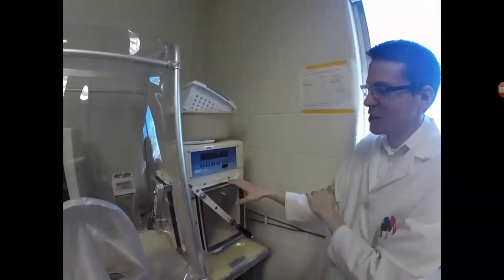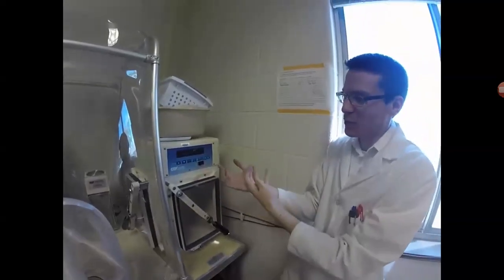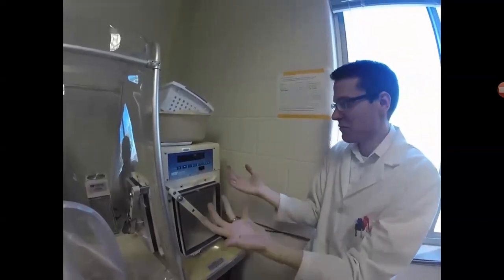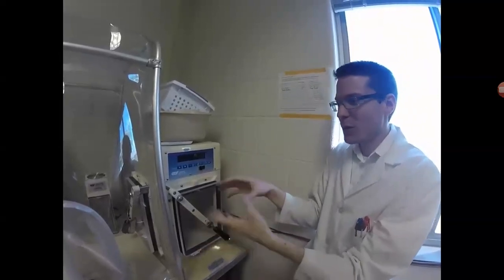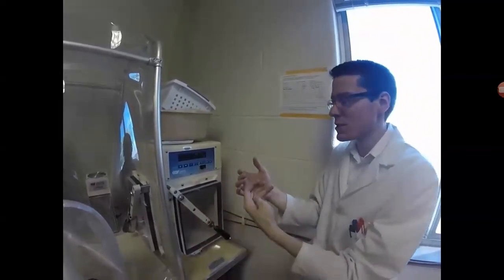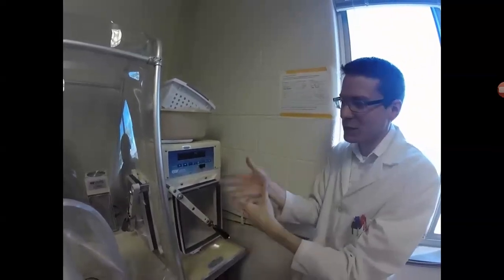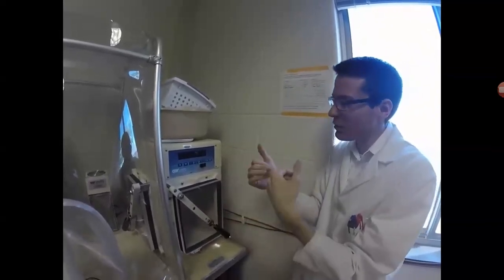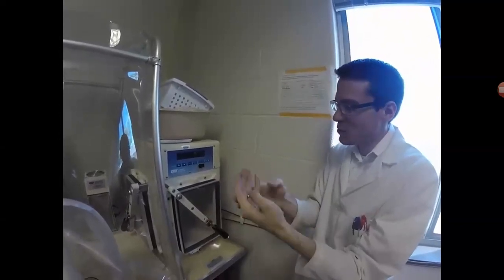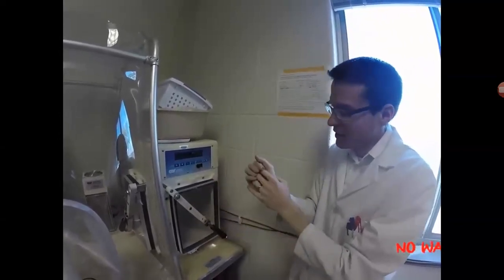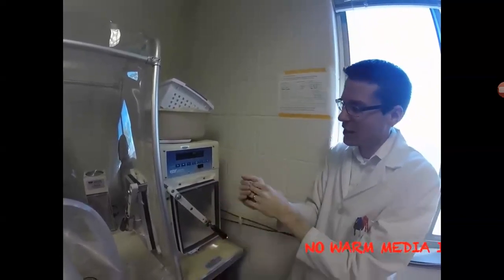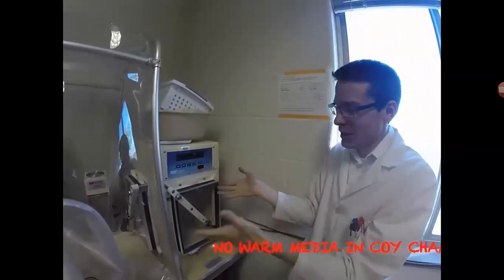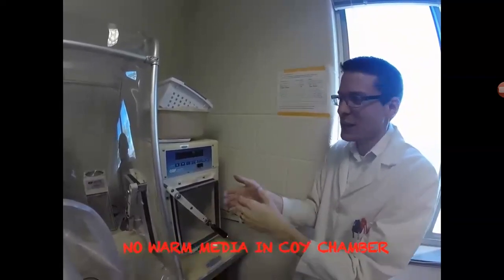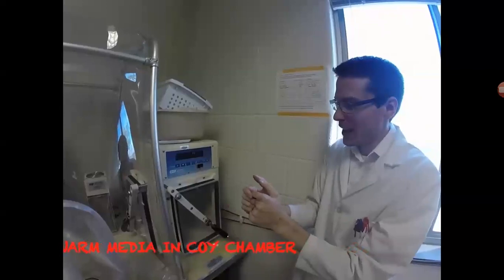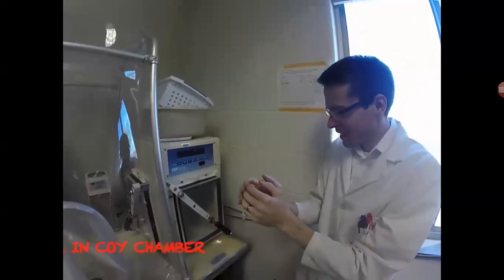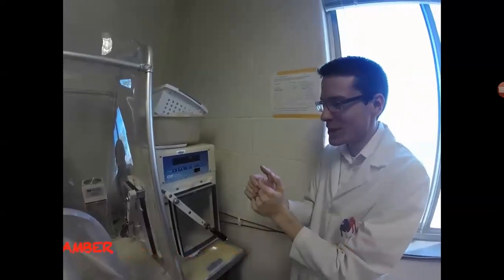A few things to mention are that it does pull a vacuum of 20 inches of mercury, which is fairly significant. So for typical things that are sealed, like media bottles and stuff like that, I will loosen the cap just to allow gas to exchange. It probably helps to remove oxygen as well. If you were to ever bring warm media in here, so let's say you took something out of the autoclave and it was still decently warm, you need to remember that under low pressure inside of a vacuum, it may have a tendency to boil. So don't do that because it's bad. And I know based on experience, so don't put it inside.